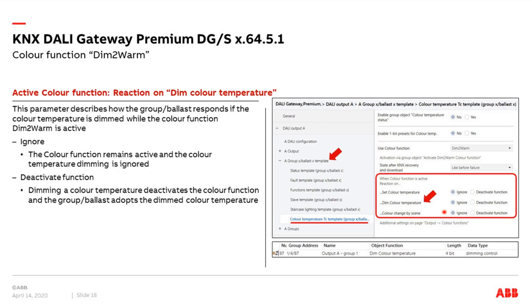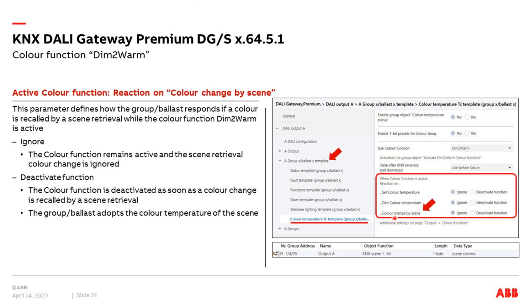Similarly, configure what happens when the device receives a relative dimming command for the color temperature — a four-bit object from a rocker dimmer — either ignore it or deactivate the function and adopt the new dimming command. And a third parameter: when someone calls a scene, should the gateway ignore the scene, or deactivate the DIMM-TO-WARM function and adopt the color temperature value of the scene? These settings apply per group or per ballast.